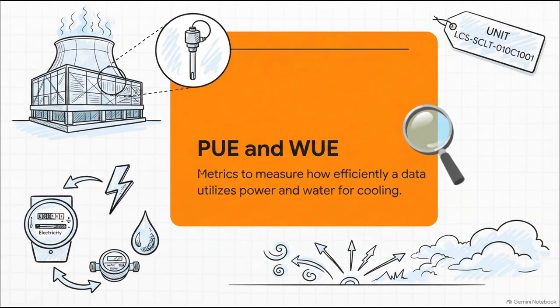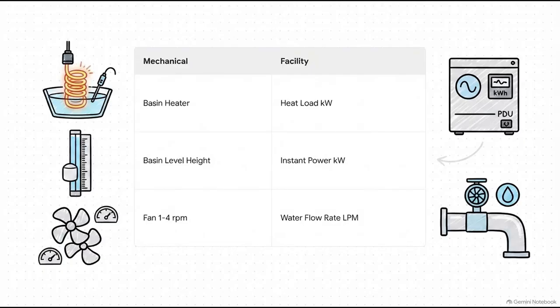That's power usage effectiveness and water usage effectiveness, which our source data measures in liters per kilowatt hour. Think of these as the high-level vital signs for the entire facility. The sensors on these cooling towers aren't just checking local temperatures, they're actively calculating these facility-wide efficiency metrics to make sure the building isn't wasting massive amounts of electricity or municipal water. This brilliantly illustrates how this tower balances the micro and the macro.